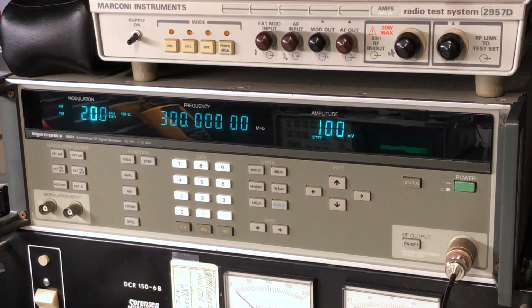Here's the RF signal generator that I'll be using to troubleshoot the audio section in the spectrum analyzer. So you can see it's set to 300 megahertz. That value is not critical, it just needs to be something within the range of the spectrum analyzer, so I just picked 300 megahertz at random. And you can see it's set to frequency modulation, 20 kilohertz deviation, and it's going to generate a 400 hertz tone. That's what it's modulating with. So in the spectrum analyzer, in the audio section, we'll actually be measuring a 400 hertz audio signal. And then you can see the output of the RF signal generator is set to 100 millivolts.